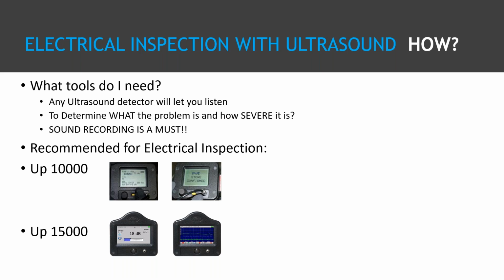Okay, so the 2 instruments we have for doing sound recordings are an UltraProbe 10,000 and a 15,000. The only real difference from a sound recording standpoint is you're able to look at the sound recordings and the time waveforms and spectrums right on the screen with a 15. The 10, you've got to record it and go take a look at it on your computer. But it's extremely important, if you're going to analyze and gauge severity, that you have sound recording.